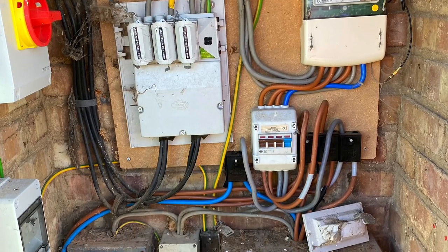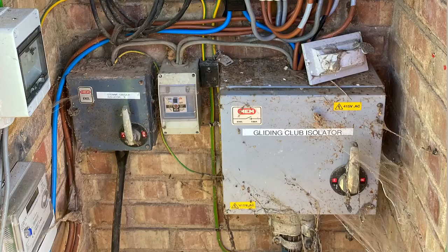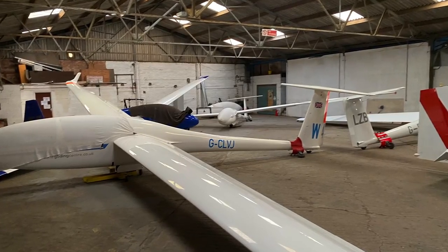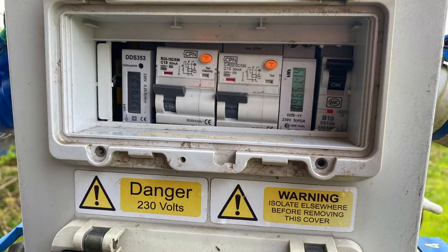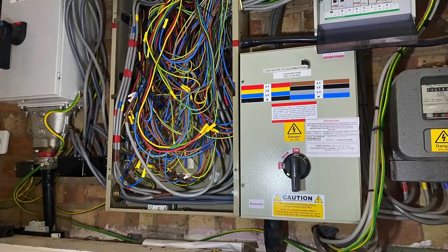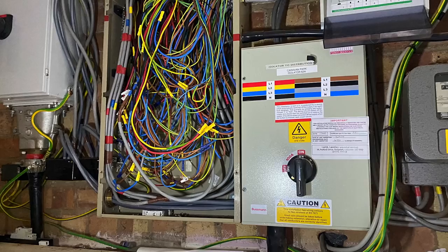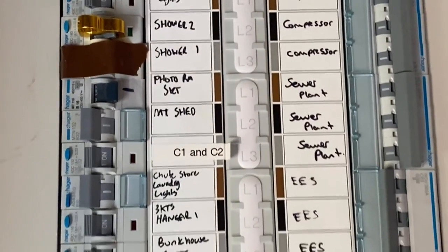We're here at a commercial site doing some rectification work off the back of an EICR done by somebody else. There's a caravan site or mobile home site here, and the PME has been exported to all of the units. Off one of the main distribution boards here, we have a labelled circuit called C1 and C2.